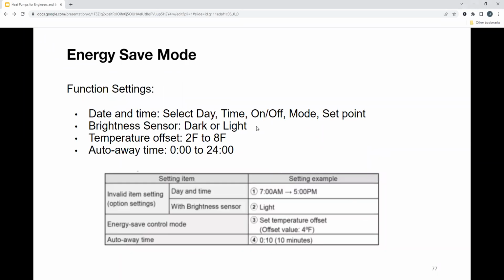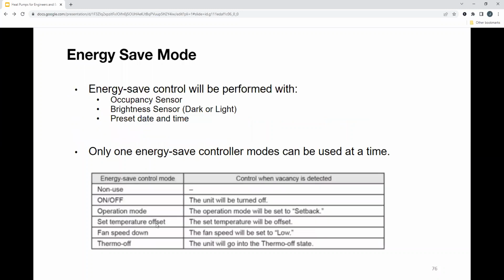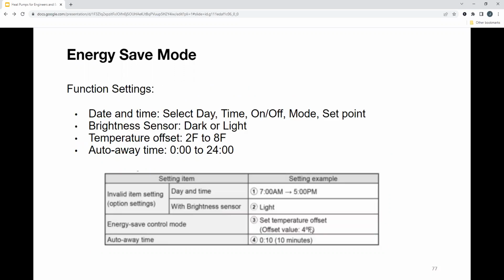Some of the function settings that you're able to do: you can go in here and say, hey, I have an office building. It operates between 7 a.m. and 5 p.m. Good, right? How do we check that? If there is a brightness sensor available on a local controller, you're able to say, all right, when it's light out, we're going to be in operation. And then when you set your energy save mode, what are we doing? A temperature offset, operation mode, on off? In this case, for an office, we're going to do temperature offset. After 5 p.m., we are going to set it back 4 degrees. And then auto away time is every 10 minutes.